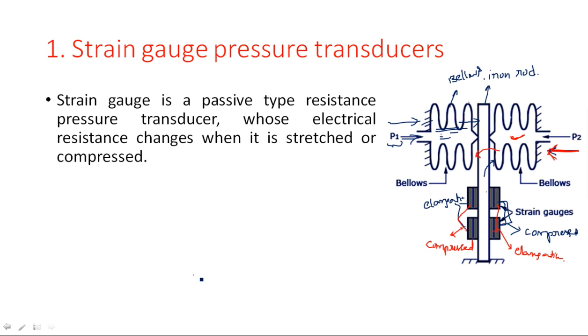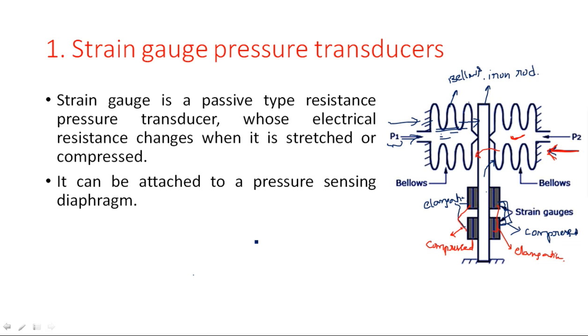A strain gauge is a passive type resistive pressure transducer whose electrical resistance changes when it is stretched or compressed. A strain gauge is essentially a resistive metal wire that has some resistance. Whenever we apply compression or stretching, the resistance of that device varies, so the electrical property varies. It can be attached to a pressure sensing diaphragm, so that the resistance varies in proportion to the applied pressure.